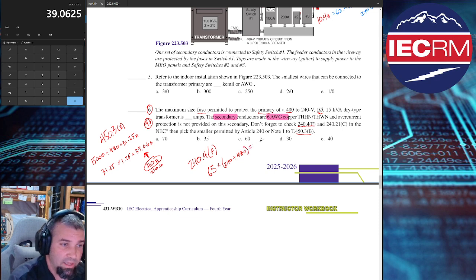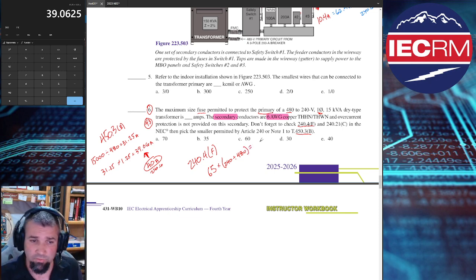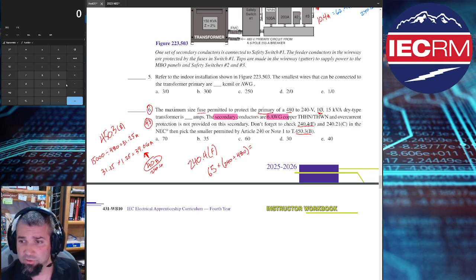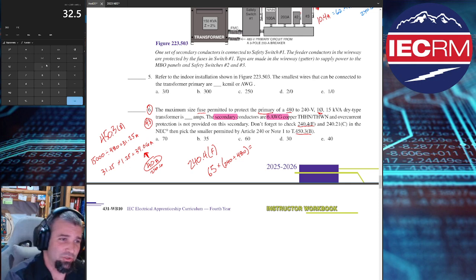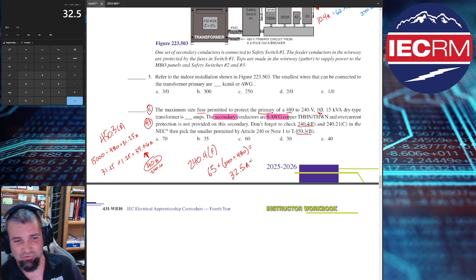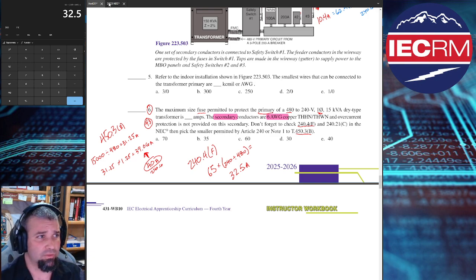Okay, you set it up just like that. 65 times, and then you open your parentheses, secondary voltage divided by primary voltage. Let's do it. 65. Do you love this yet, or is it a hate? 65 times 240 divided by 480. I'll close those parentheses out. It's 0.5. You hate it? Oh, come on! 32.5 equals 32.5 amps. Okay. Strongly dislike. There you go. Okay. Now can we round that up or down? That's the next question we have.